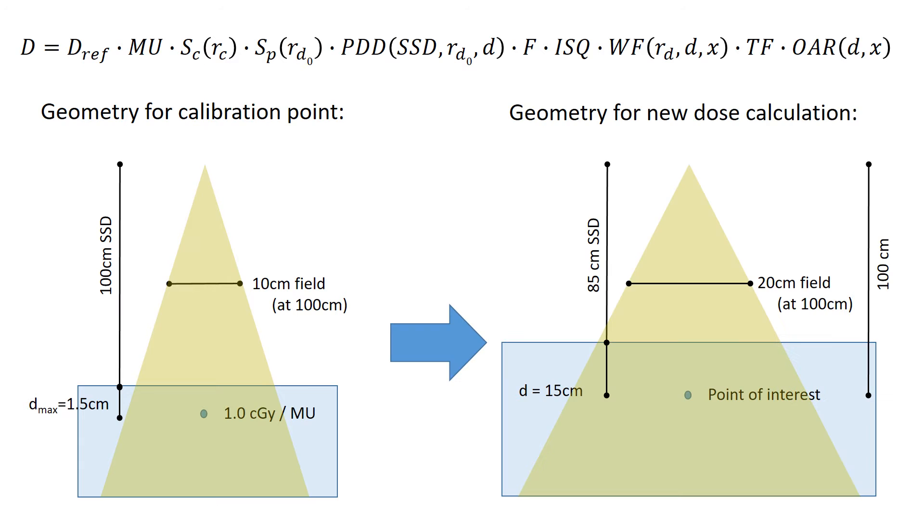And we want to calculate dose in a new situation, which has a new SSD, 85 cm, a new depth, 15 cm, and a new field size of 20 by 20 cm.